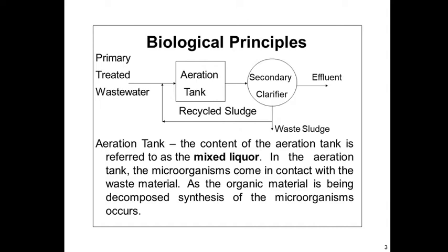So in the reactor, the microorganisms convert this soluble organic matter into energy, new cell mass and CO2, carbon dioxide gas. That is, organic matter is converted into simpler forms. The aerobic environment in the reactor is maintained with the help of an aerator. Either we can use a diffuse aerator or a mechanical aerator to keep the water, organic material and culture in suspension.